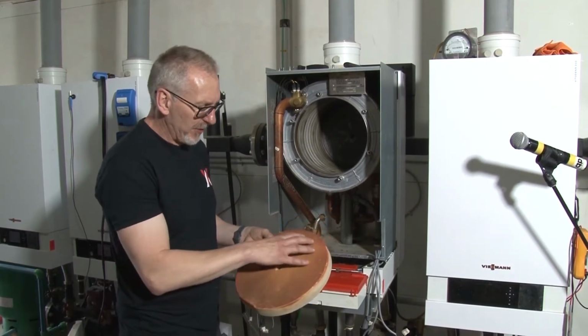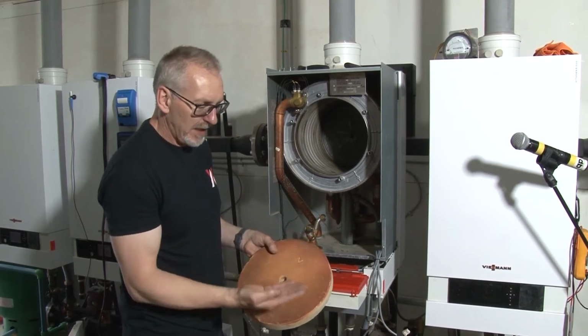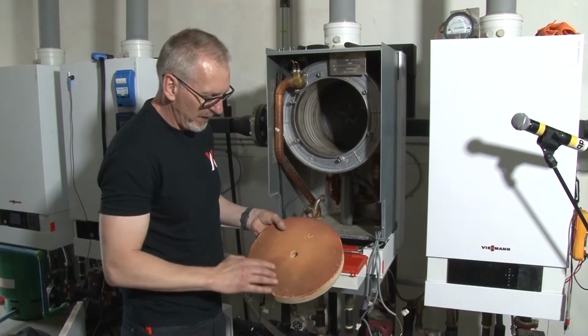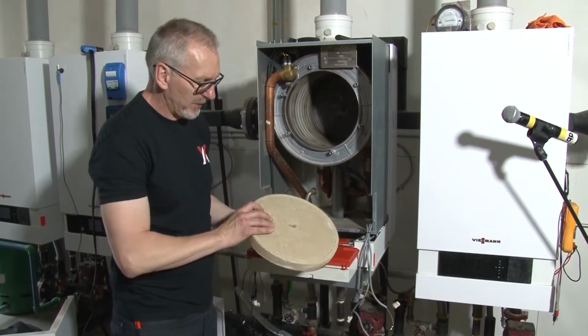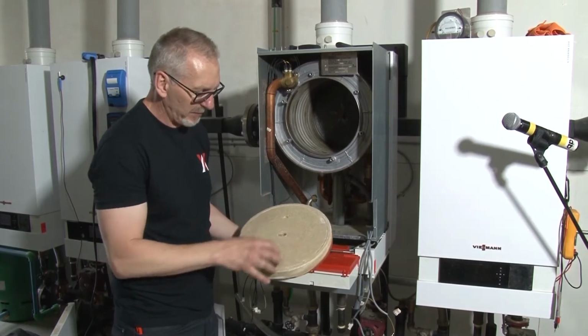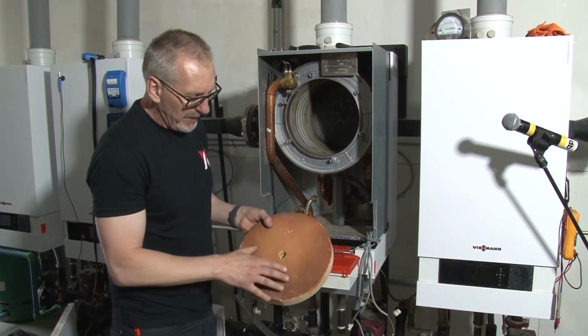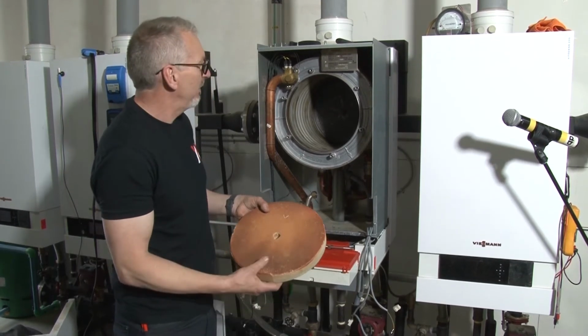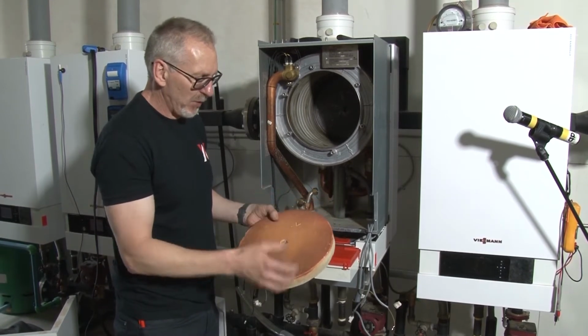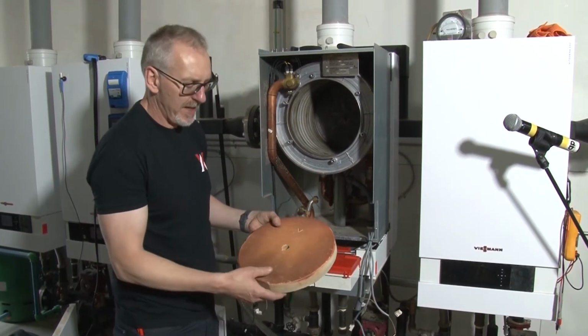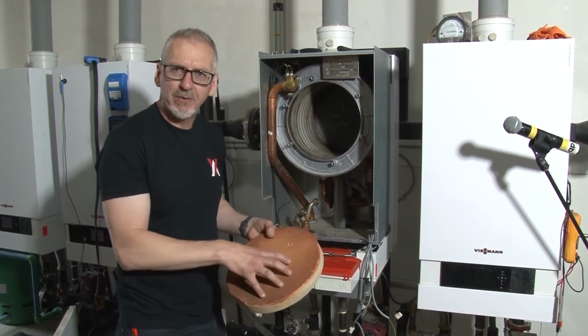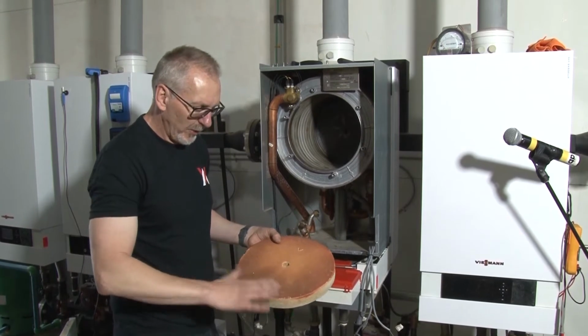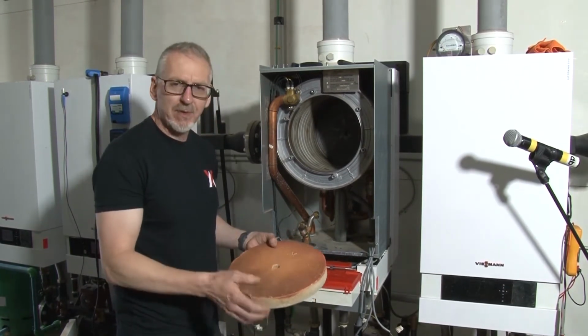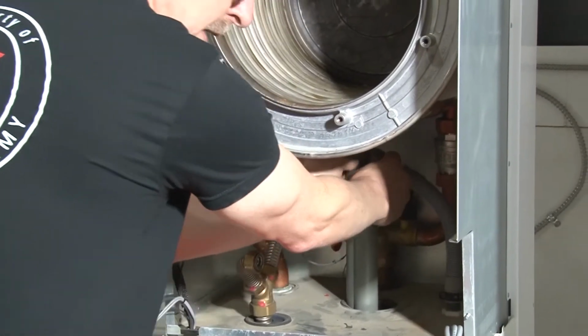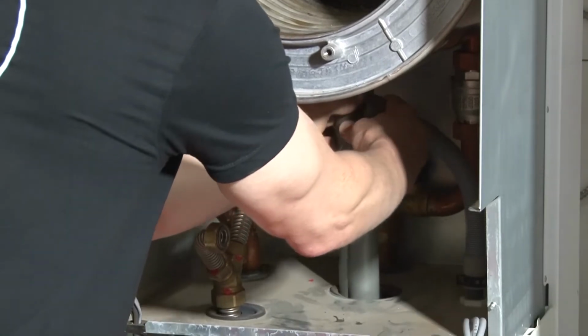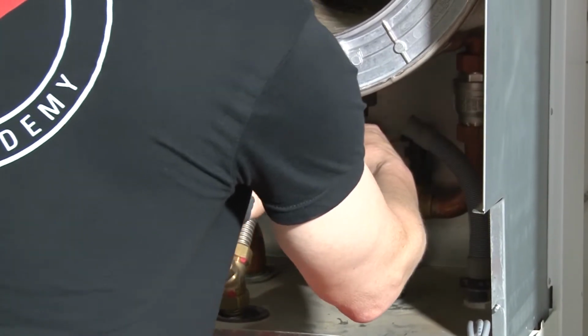But there's also on this one here, I noticed there's some contamination as far as dust that we can see on the ring here. It's normal to see these usually as the color you see in the back. This is like a brand new refractory, this nice beige. Flip it over and you see this orange bit here. That's from air coming in for combustion. And of course when it burns off, it's the same idea as what we see on the water side. There's some mineral here basically coating the surface. It's not hurting anything. But over time it builds up and it can be a problem. There's a compression ring on the top here. Might be a little difficult to see at the top, but I'm just basically backing that off. And I can pull the P-trap right out here.